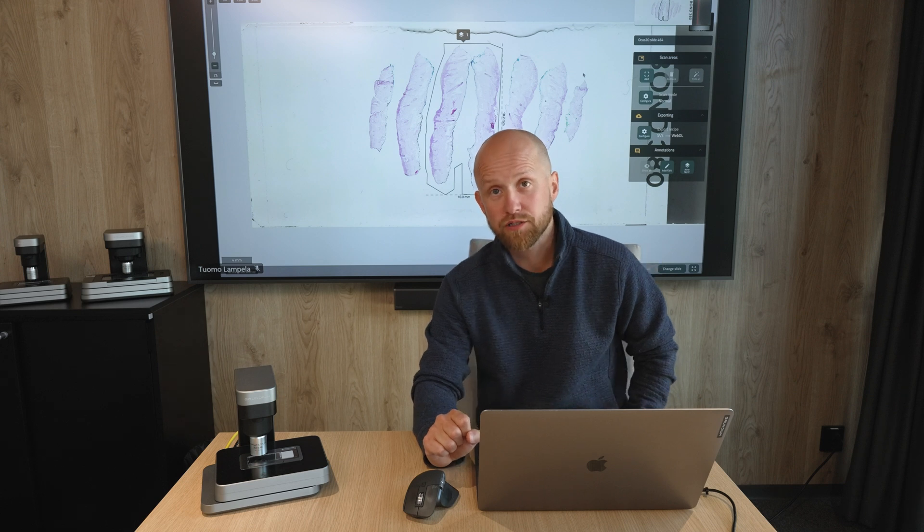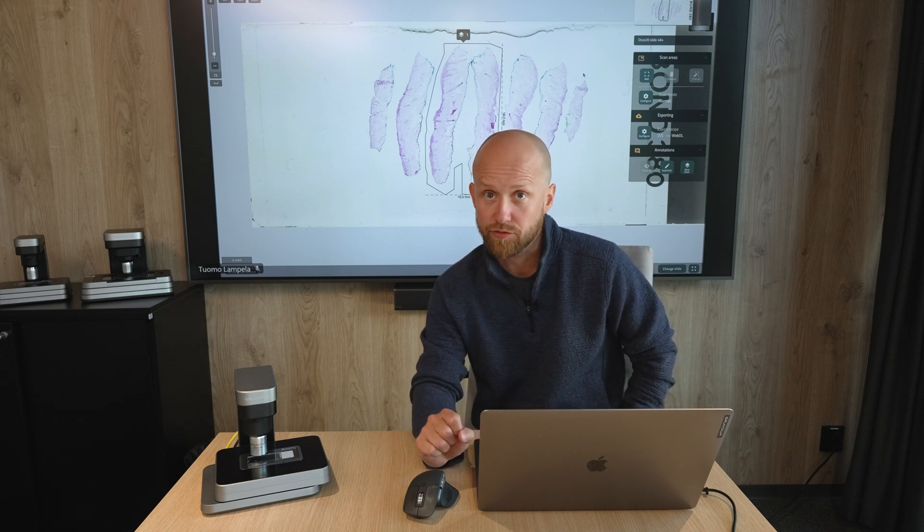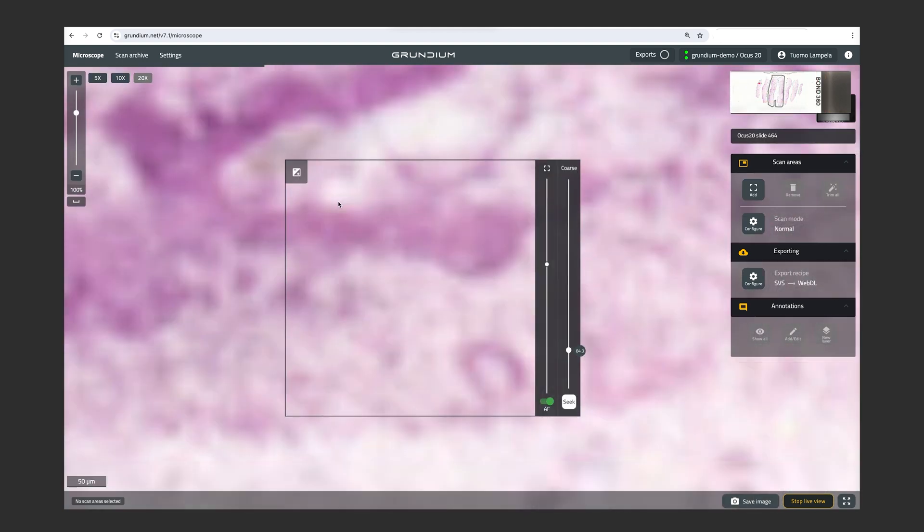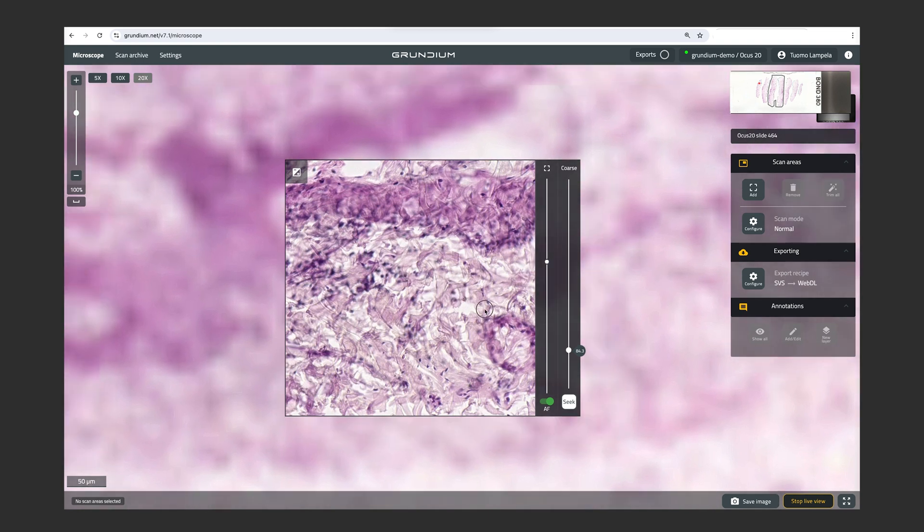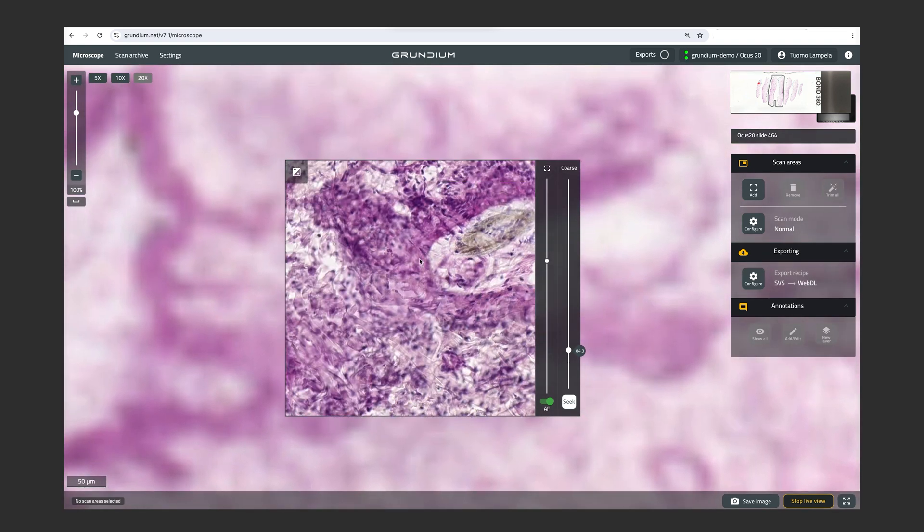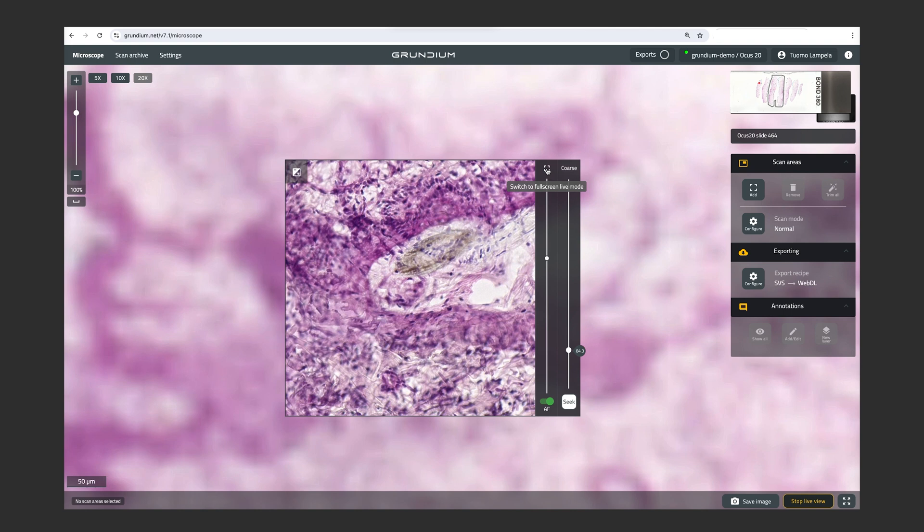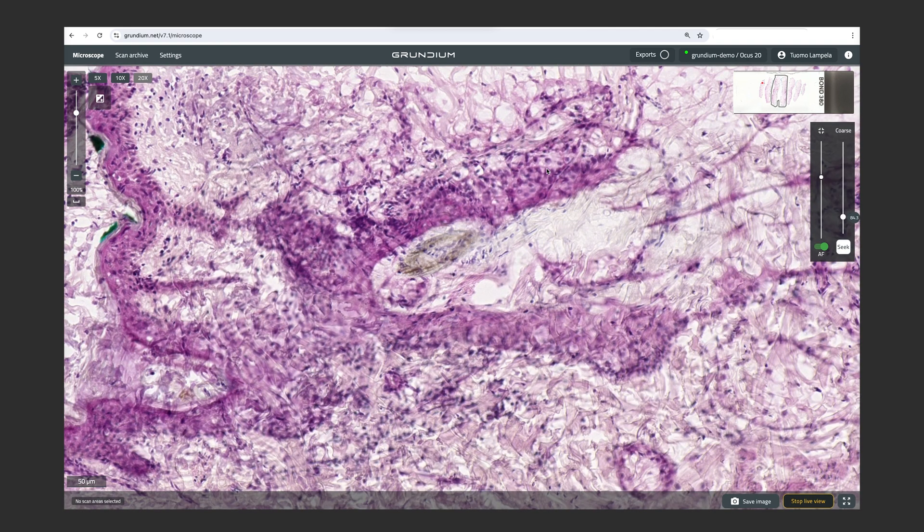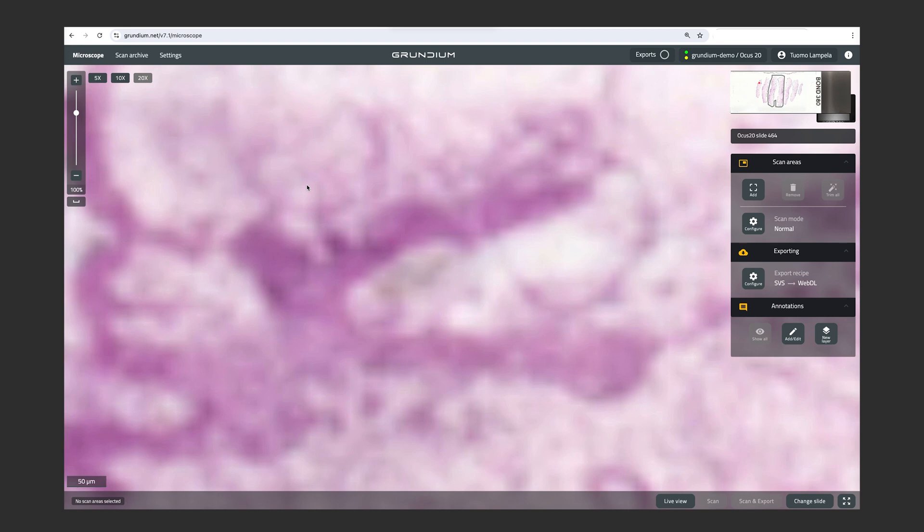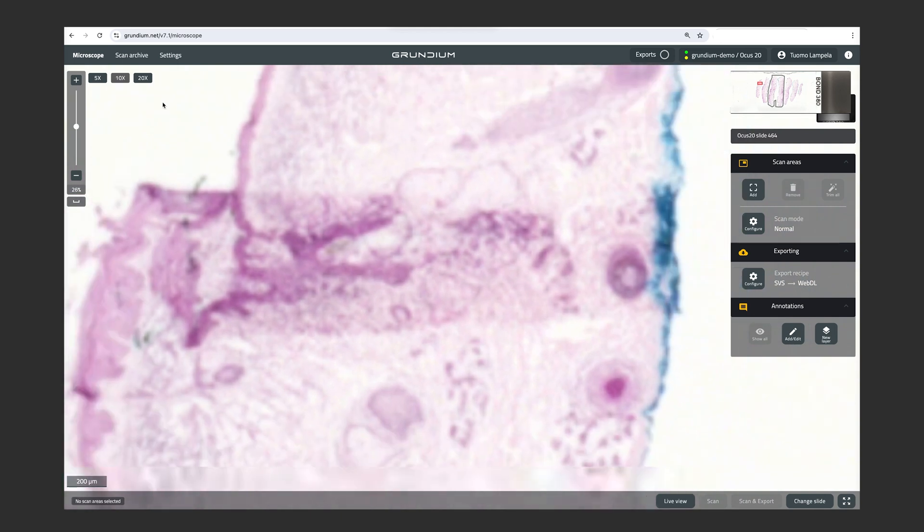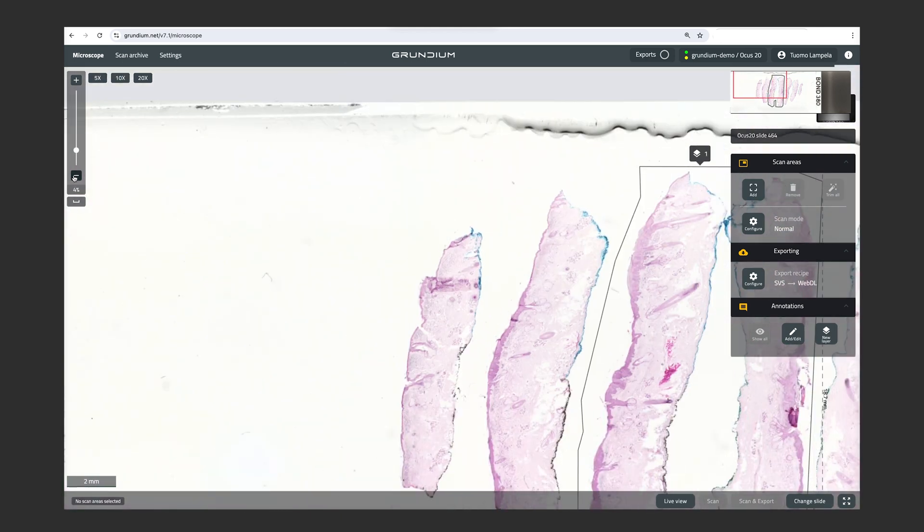We do also have the option to live view the samples without scanning them at full resolution. And that happens by clicking the Live View button on the bottom bar. And then we choose the area we want to look at. And then the scanner automatically focuses into the sample. And we can also move around by dragging. As you can see, it moves in the background. And then focuses in the area that we've chosen. And we can also turn that into full screen. And we can see the whole area live. So this is not scanned. And that can be seen if we stop the Live View. And this shows the area from the overview image. So it's not scanned. So that's something that some of our customers also use.